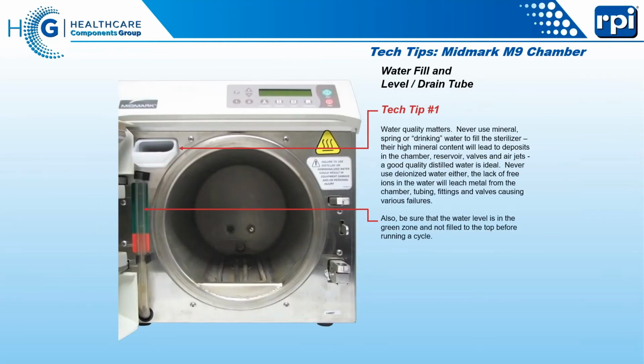Okay. So water quality is very, very important with sterilizers. You cannot use spring water, mountain water, drinking water, any of those varieties. You should only use distilled water. This says distilled water on it, bought in Walmart. For any piece of medical equipment that doesn't specifically say it, you should never use deionized water in anything. Deionized water will leach the ions out of the chamber, out of all the copper tubing, out of all the brassware. Eventually your machine will fail and you will wind up replacing a lot. So deionized water, very, very bad. Tap water, never, very, very bad. Distilled water only.